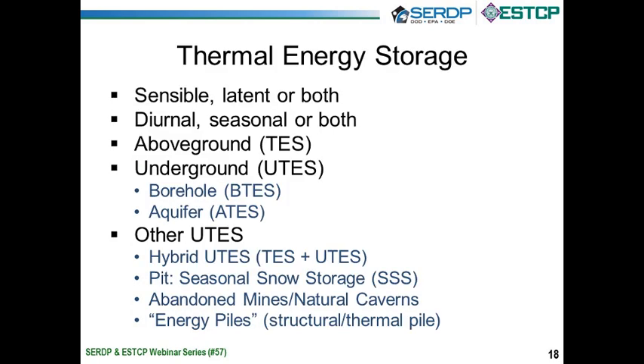So looking at thermal energy storage, generally you can divide that into sensible storage, as in it makes sense. It is a change in temperature. You're storing thermal energy by either lowering or raising the temperature of some media, solid or liquid. If it changes phases, then that would be considered latent storage, latent meaning hidden. So it might be a change from a solid to a liquid or a liquid to a vapor, or you can do both. Our project was strictly sensible, but certainly it could have incorporated latent if we had chosen to. The thermal energy storage that we'll be discussing today is both diurnal, as in daily storage, and seasonal storage, as in winter or summer. Thermal energy storage can be one or both, as this project was both.